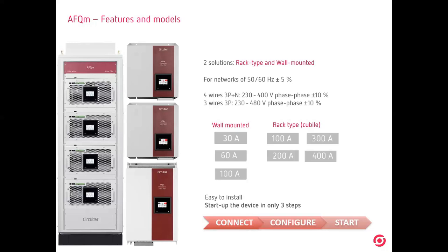We have active filters called AFQM, okay? Rack type or wall mounted, able to be connected in 4 wires or 3 wires, 400 volts or 480 volts, okay? And we have wall mounted in 30, 60 or 100 amps, or rack type, like a cubicle, okay? 100, 200, 300, or 400 amps with four modules, right, of 100 amps each module. You can connect up to 100 devices in parallel. So you can have as much current as you need in any installation, okay?